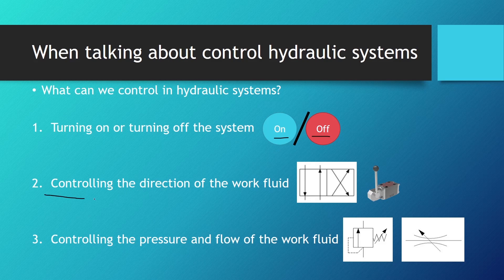Second, we can control the direction of the work fluid with directional control valves. If we want cylinder extension, we have to direct the fluid to the front of the piston; if we want cylinder retraction, we have to direct the fluid to the back of the piston, as we saw in one of the previous lessons. This is exactly what directional control valves do — they enable us to direct the fluid flow.